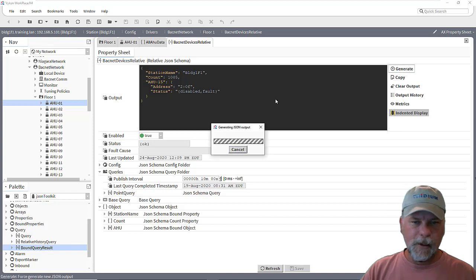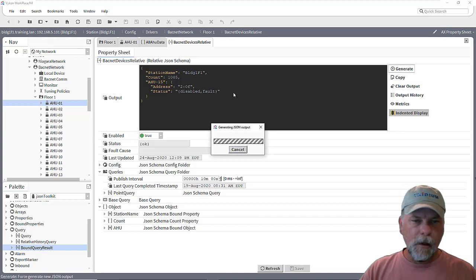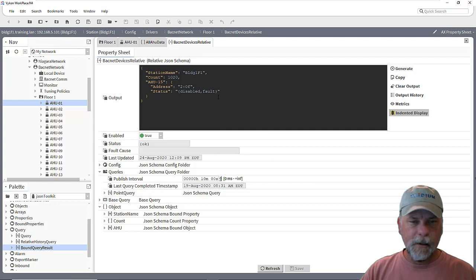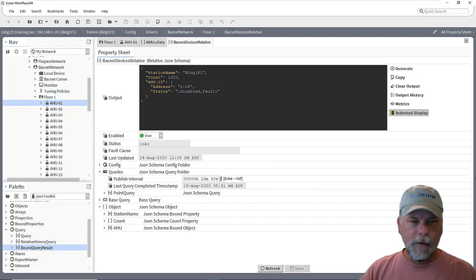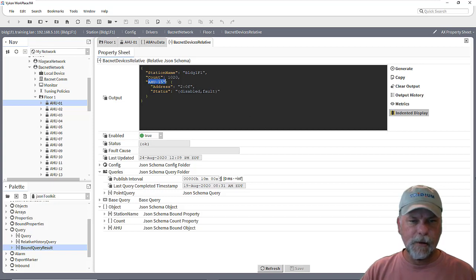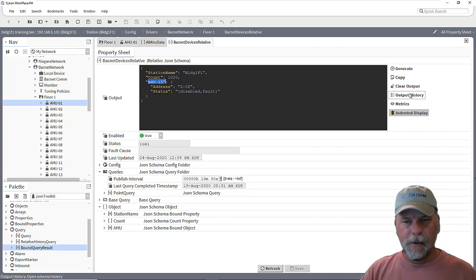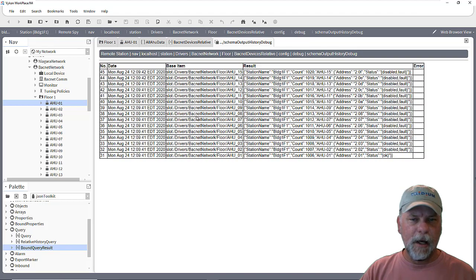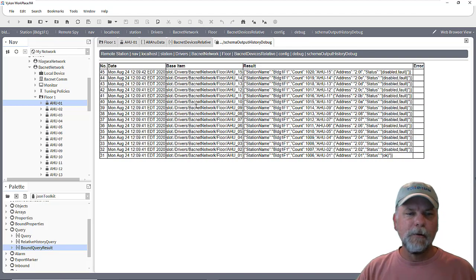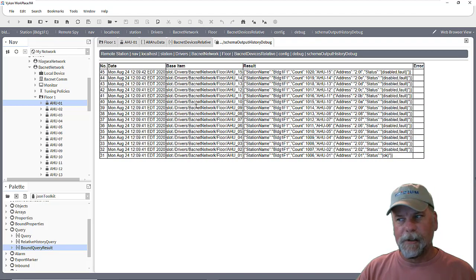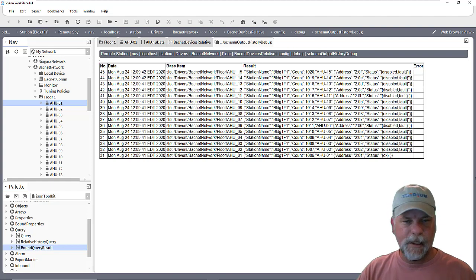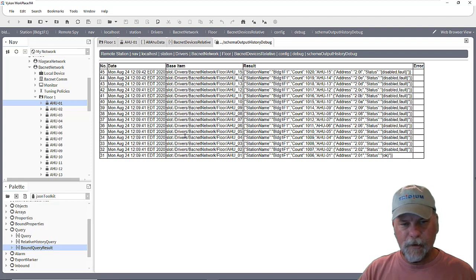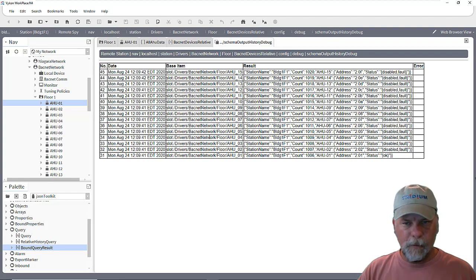So when I generate the schema it'll go through and you might not really see it updating here. But you see the last result is AirHandler 15 with its MAC address and status and that sort of thing. Now there's an output history button you can click over here and this will open another tab with a spy view. It'll show you the last X number of executions and the default is 10. I've changed the default on the property sheet under the config to 15 so I could see all the messages that were processed.